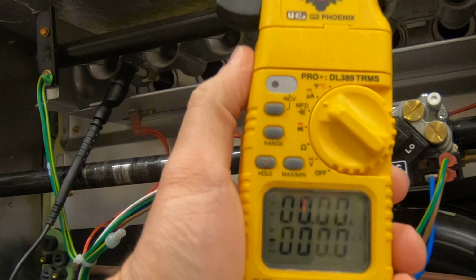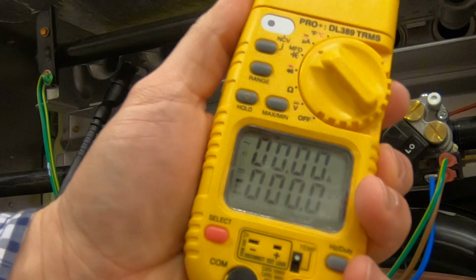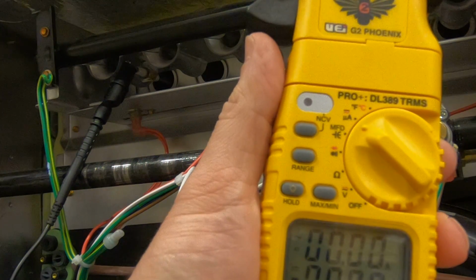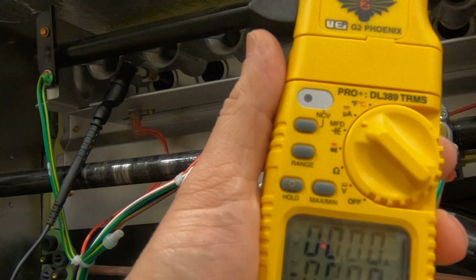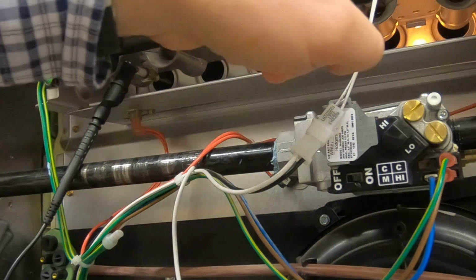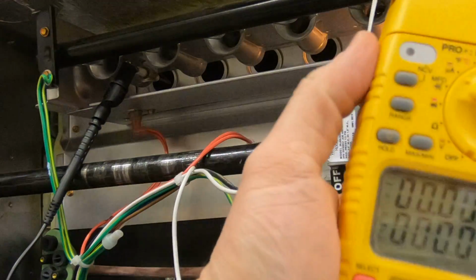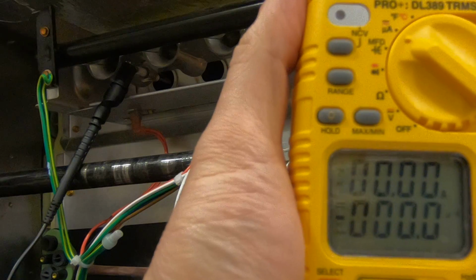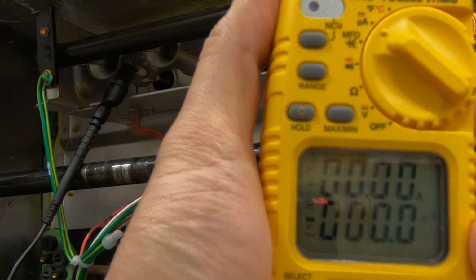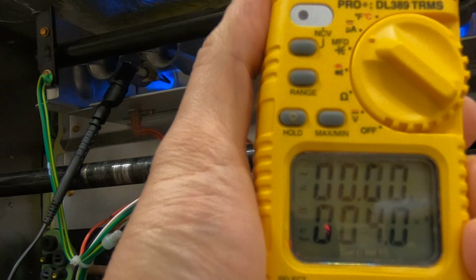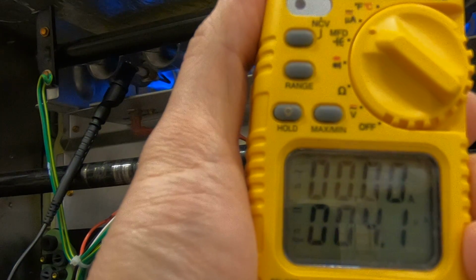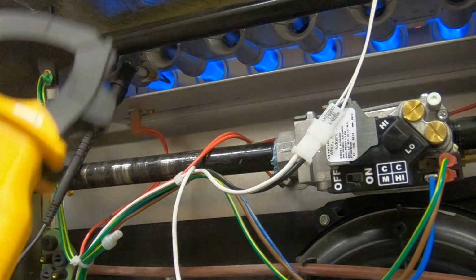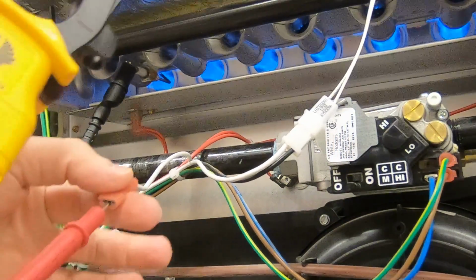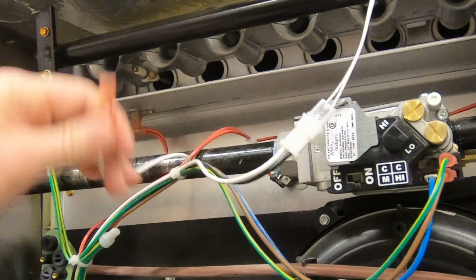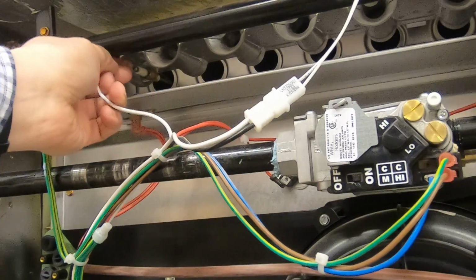Okay, the machine just went through its cycle. We're going to see it turn on using the DL389. See the igniter starting to light. You'll see the flame go across as it reaches the sensor. As it reaches the sensor, you'll see the numbers change. You can see 4.0, 4.1. So that's how you read the flame sensor with the meters we have at Building Automation. When you're complete, just unplug it here and here, and then plug this back in and turn the thermostat off.